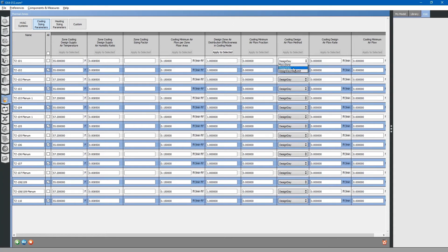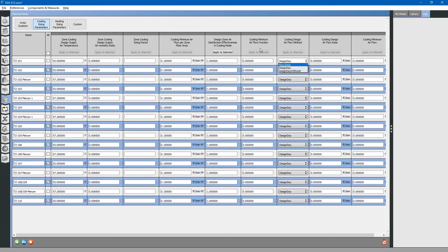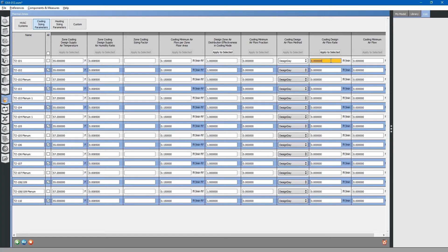Design day or design day with limit. If you use design day with limit, it sets the design air flow based on design day. It also includes minimum air flow per area or minimum air flow rate column. Also, you can hard code the cooling design air flow rate for this zone if you know exactly what it is per the design.